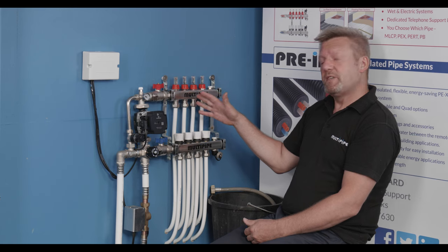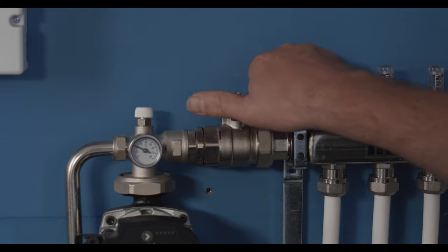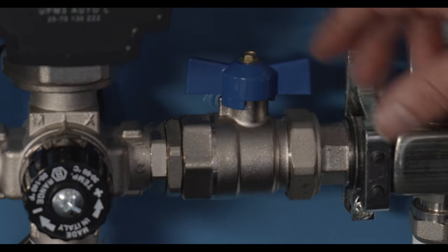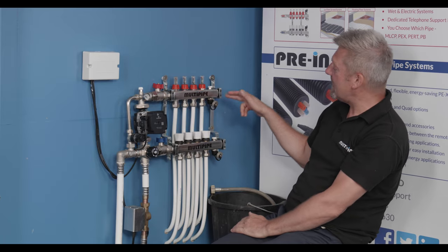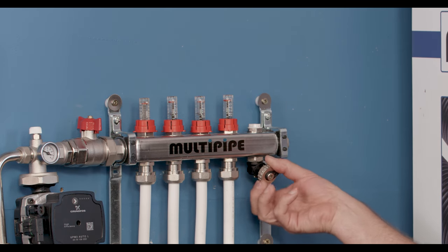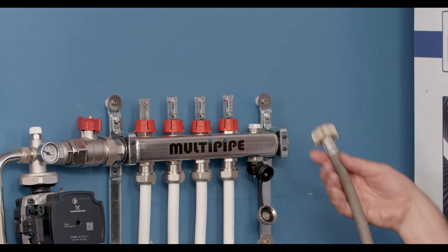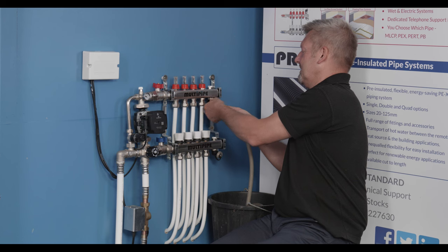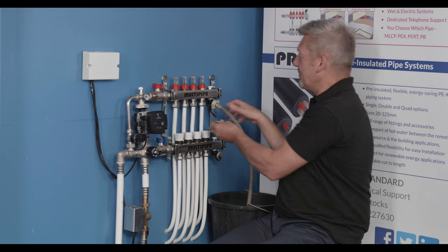We're going to work on this particular four port Multipipe manifold. We're going to start by isolating the manifold — turning off the flow and return ports — and then we need to depressurise the manifold. We'll do that using the filling vent point at the end, unscrewing the cap and discharging it into a bucket. I'm just going to attach a hose pipe on the end and depressurise the manifold into this bucket here.